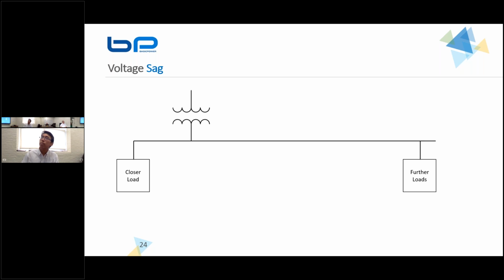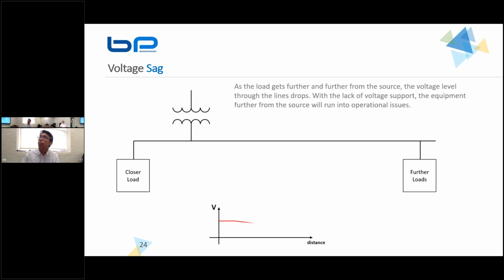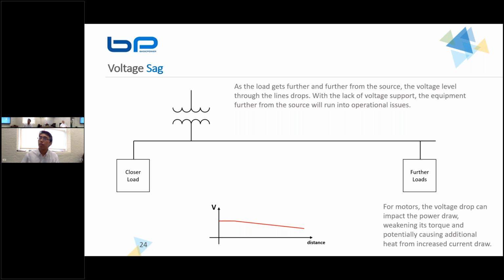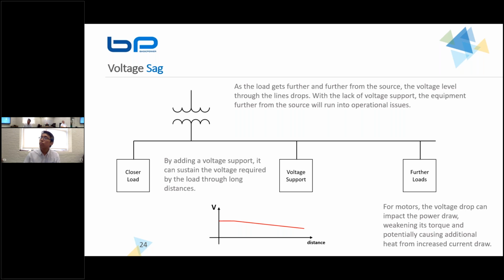Another thing to note is that in ports, generally you have a very large site and the utility needs to deliver power to you guys. So the closer loads would be able to receive the voltage as intended, but the loads that are further away would start seeing a voltage drop. So if you have crane operations or any motor applications or even HVAC at a site that's really far from your distribution, you start seeing voltage drop, and that can impact the torque and even cause additional heating from the current draw. So the way to prevent this issue is to provide voltage support in the middle, and this voltage support can sustain that energy throughout the long distance, and you can maintain a relatively good voltage while you're operating from far distances.